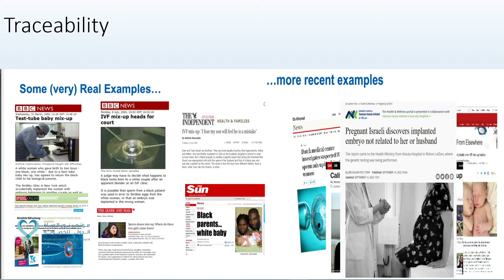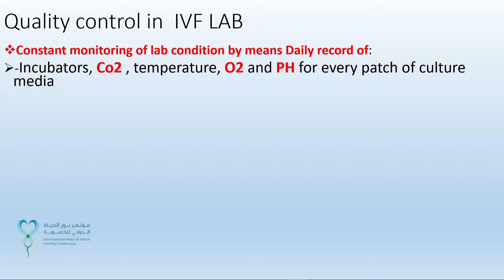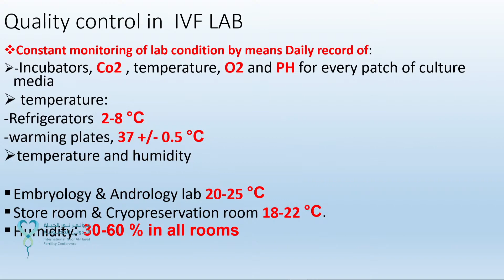The Witness system is monitoring and recording all activities of workstations where samples are moved from one dish to another all year round. Quality control in the IVF lab: there are some quality controls that have to be done on a daily basis in a lab, such as incubators, CO2, temperature, oxygen, and pH. The temperature of refrigerators needs to be between 2 and 8 Celsius. For warming plates, it needs to be 37 degrees plus or minus 0.5. The temperature and humidity of the embryology and andrology lab has to be between 20 and 25 degrees. Storeroom and cryopreservation room has to be between 18 and 22 Celsius. Humidity has to be between 30 and 60 percent at all times.